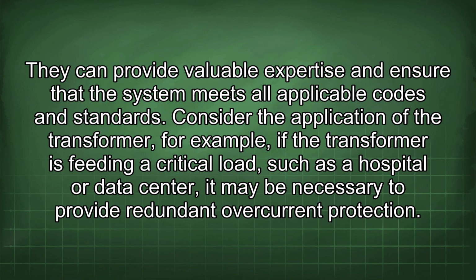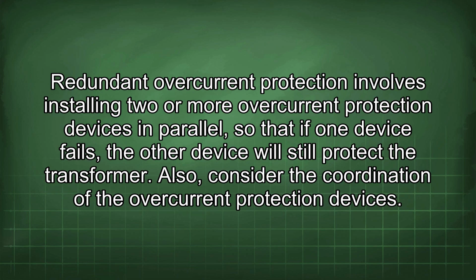Consider the application of the transformer. For example, if the transformer is feeding a critical load, such as a hospital or data center, it may be necessary to provide redundant overcurrent protection. Redundant overcurrent protection involves installing two or more overcurrent protection devices in parallel, so that if one device fails, the other device will still protect the transformer.